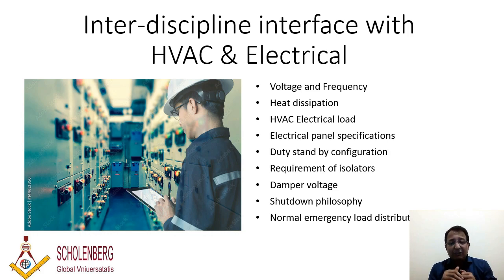Then normal and emergency distribution load also needs to be done, because when an emergency happens, all your crew on the platform take refuge at a particular place - called a temporary refuge - and you need to keep certain equipment running to maintain cooling and pressurization for that zone. In that situation, you don't want your laundry fan, kitchen fan, or toilet fan running - you can tolerate those being off for 4 hours.